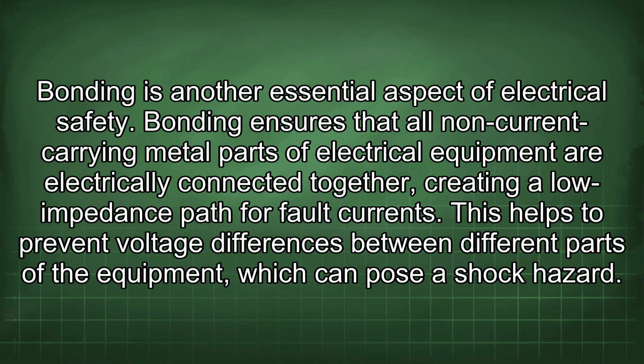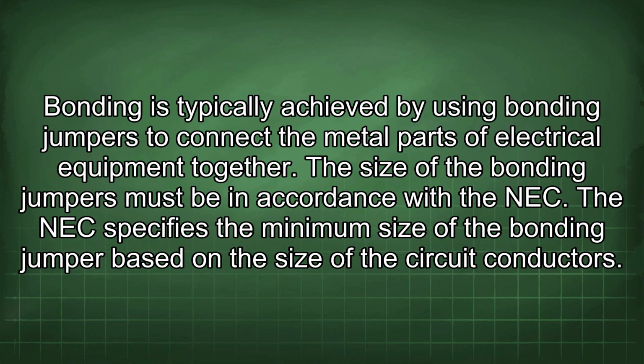Bonding is another essential aspect of electrical safety. Bonding ensures that all non-current carrying metal parts of electrical equipment are electrically connected together, creating a low impedance path for fault currents. This helps to prevent voltage differences between different parts of the equipment, which can pose a shock hazard. Bonding is typically achieved by using bonding jumpers to connect the metal parts of electrical equipment together. The size of the bonding jumpers must be in accordance with the NEC. The NEC specifies the minimum size of the bonding jumper based on the size of the circuit conductors.